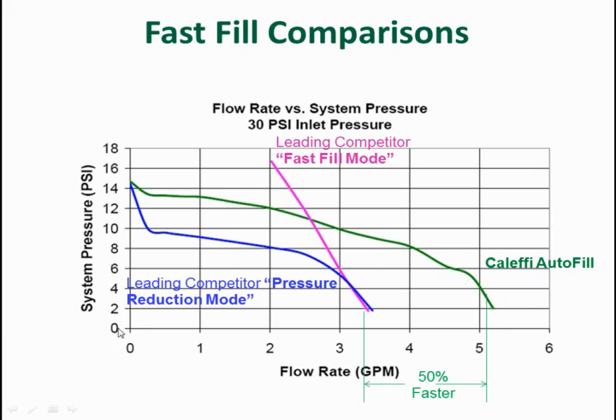So as the pressure in the system starts coming up, you start filling at 0 pounds pressure. As your pressure starts coming up, notice that our valve stays out here at a pretty high flow rate. We're still at 3 gallons a minute, even if the system pressure is starting to get up to 10 pounds. Let's say we've got it set for about 14.5 pounds fill pressure on this job. You can see that we're going to fill that at a fast rate.